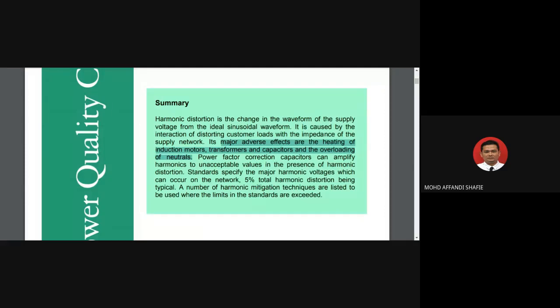So how do they reduce it? Power factor correction capacitors can amplify harmonics to unacceptable values in the presence of harmonic distortion. The standard specifies the major harmonic voltage which can occur on the network, with 5% total harmonic distortion being typical.